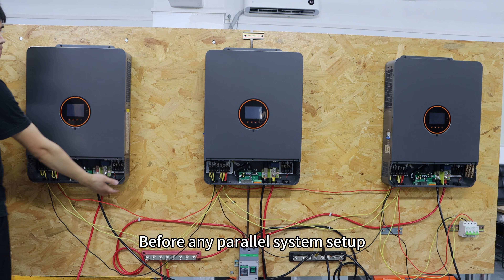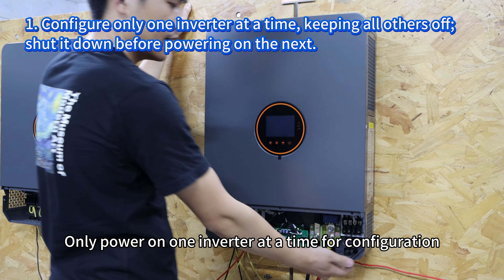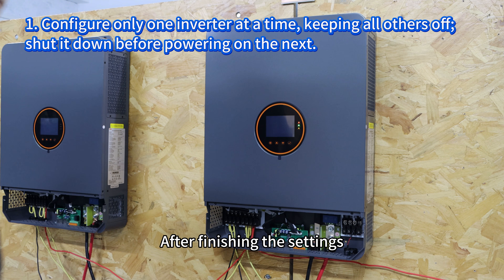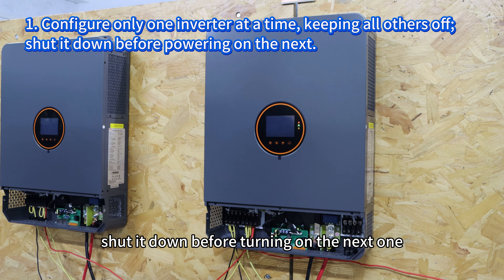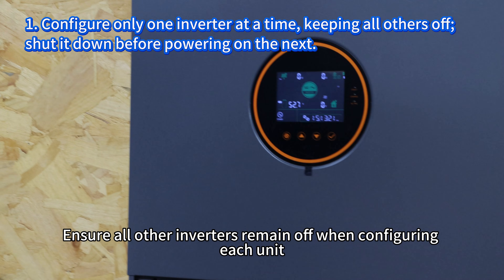Before any parallel system setup, there are two important reminders. Only power on one inverter at a time for configuration. After finishing the settings, shut it down before turning on the next one. Ensure all other inverters remain off when configuring each unit.